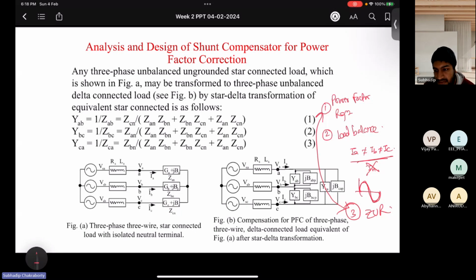If you want power factor regulation from a substation perspective, then you can do power factor regulation and design your components accordingly. So what will be the value of the components? Your focus should be on that. If you want to do power factor regulation, the component value will be different. If you want to do load balancing as well as power factor regulation, the component value will again be different, because your aim will decide what component value you require for these shunt compensators across the phases. For that, we have calculated the value of these compensators.